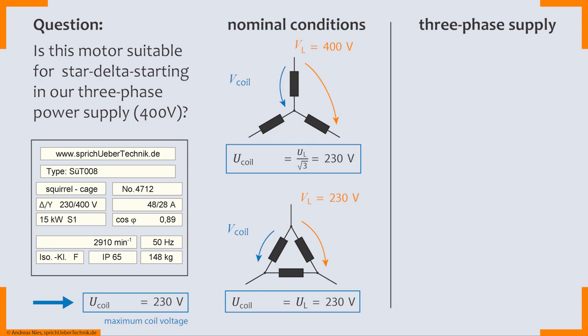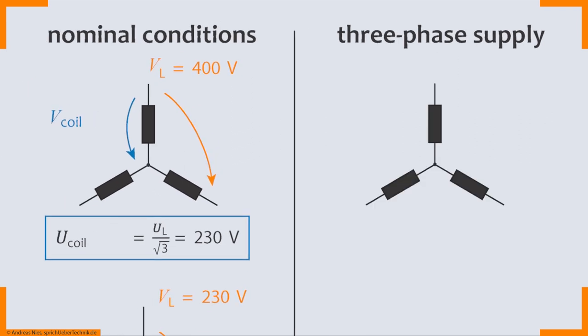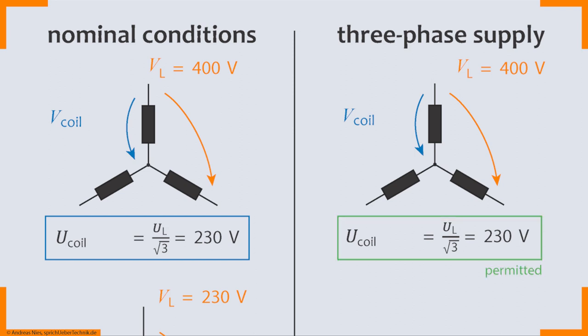Our next step is to look at it in the context of the power supply. German public power supply is three-phase AC with phase-to-phase voltage of 400 volts. For star connection this would result in a coil voltage of 230 volts. And that is the nominal conditions we figured out earlier, as you can still see here on the left hand side. And this would obviously be permitted here. So I could operate this motor without damaging it in the German public power supply with 400 volts phase-to-phase at 50 hertz grid frequency in star connection.